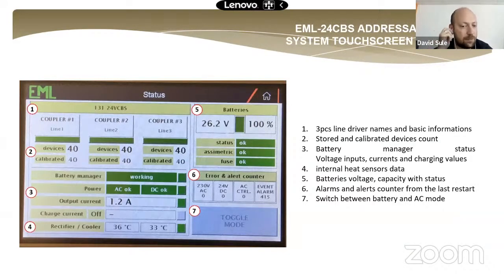On number 7, this button is disabled at the moment, because if we connect our programming software to the panel during maintenance, we can enable this button during the maintenance session. If this button is enabled, we can manually turn on all of the lights, and the panel will switch to battery mode. So we can simulate the full load battery situation. So when the AC230 is missing from the panel and one of the sub-DBs gives information and all the lights are turned on, we can simulate this event with one simple button.